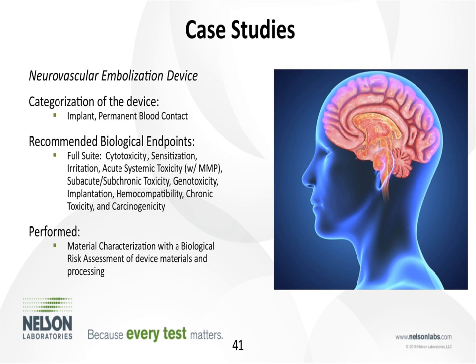We did happen to recommend to the sponsor that cytotoxicity, this is the cheapest and quickest test, be performed. Unfortunately, they did not have enough devices for testing at that time, and we also recommended that they may need to do a nickel leaching study for the nitinol material. Now, this was successfully applied outside the United States.